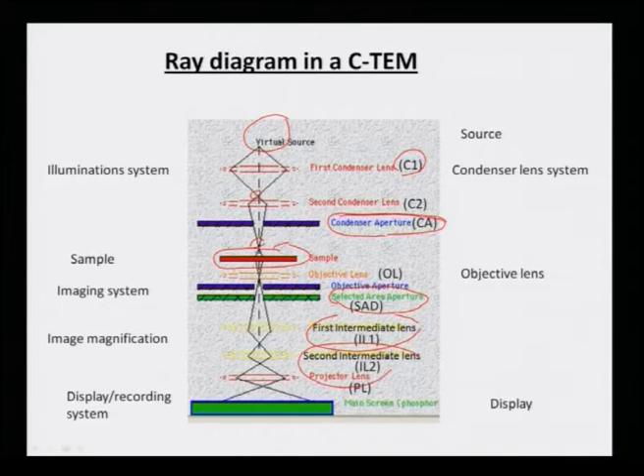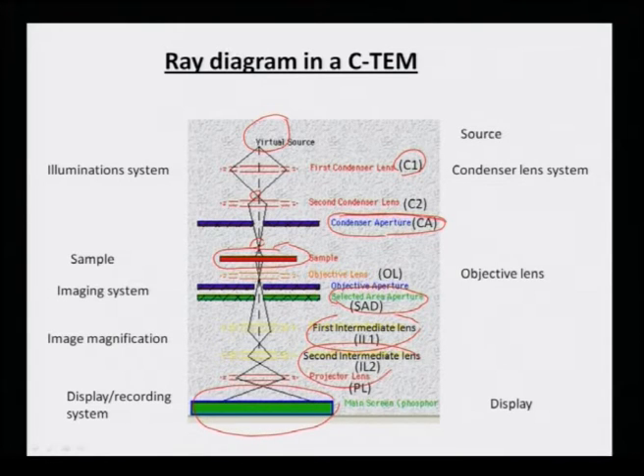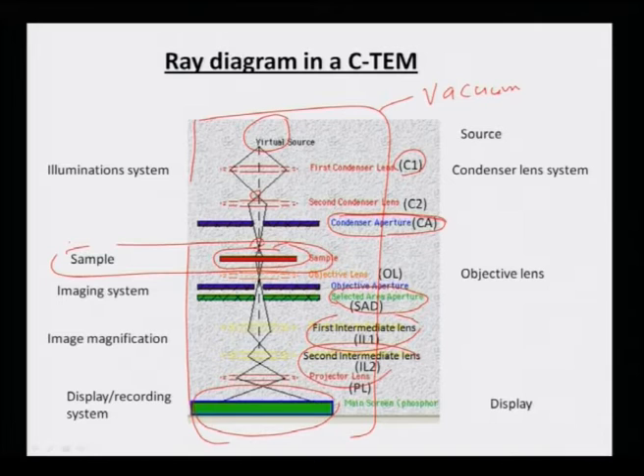So it is not as complicated as it looks. The electrons cannot be seen by the eye, so when electrons fall on a phosphor screen, we can see the image or diffraction pattern. That is why the person sits and looks at the screen at the bottom while the microscope is running with a sample in the column. The whole column must be under high vacuum because electrons cannot travel in air. Samples must also be thin enough so that electrons can pass through and diffract.